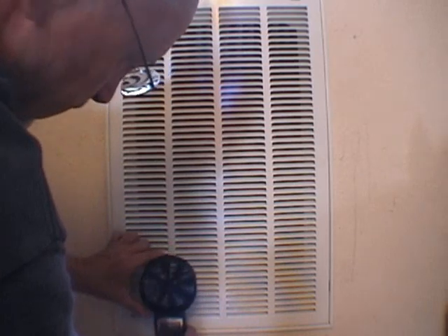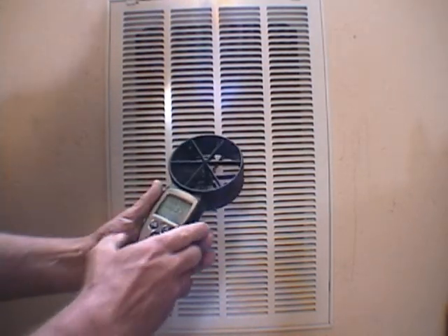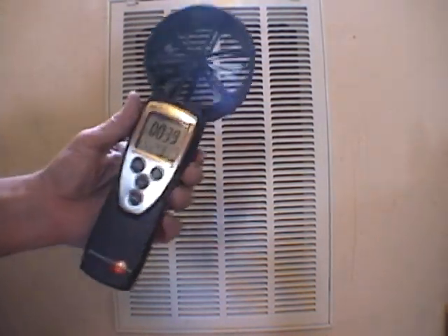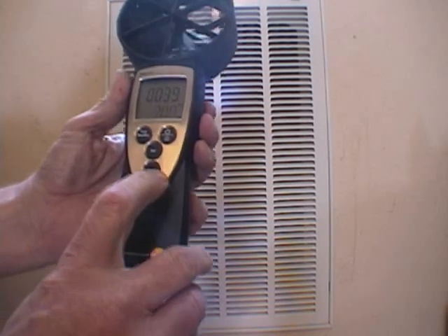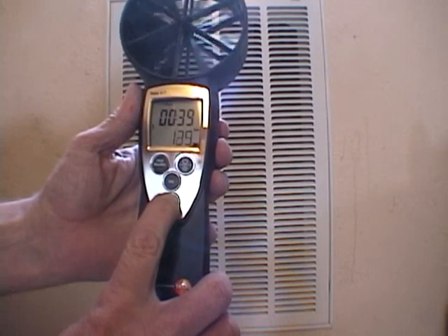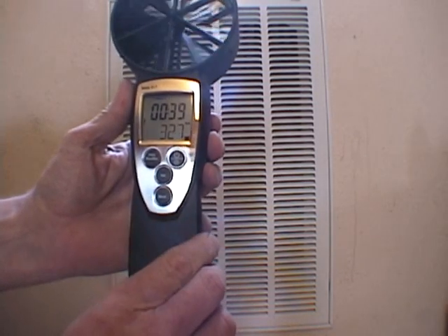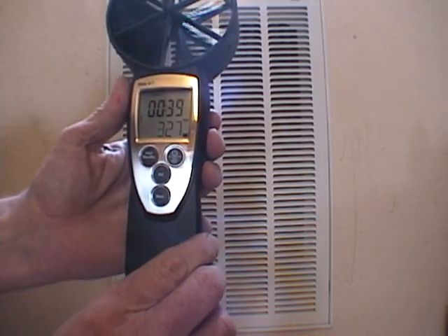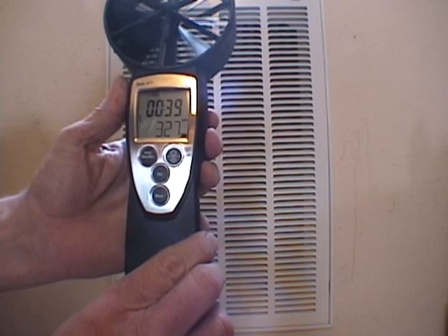When I get to the end, I push my timer again. That stops everything. So now we're at 39 seconds for this traverse. When I push this mean button, it's going to give me the average feet per minute. So this grill is 327 feet per minute.